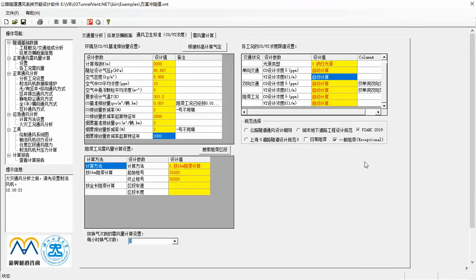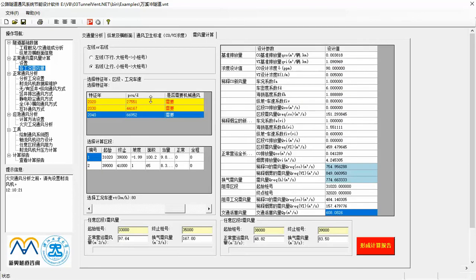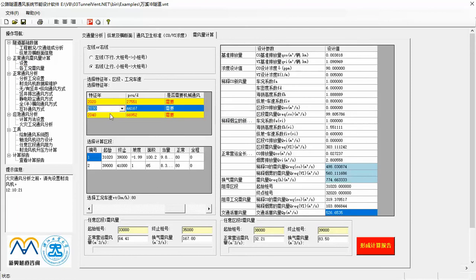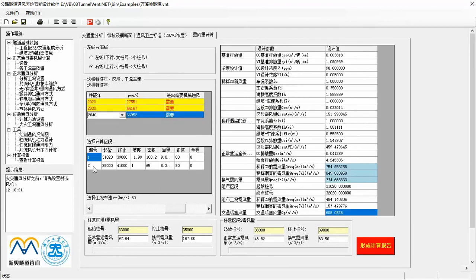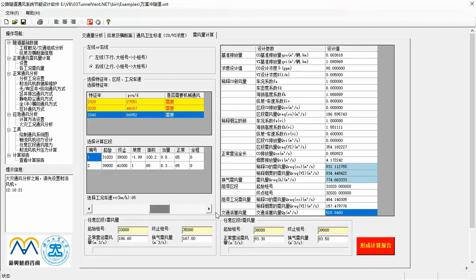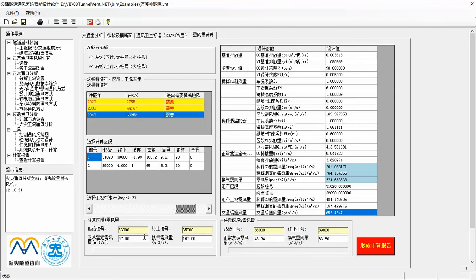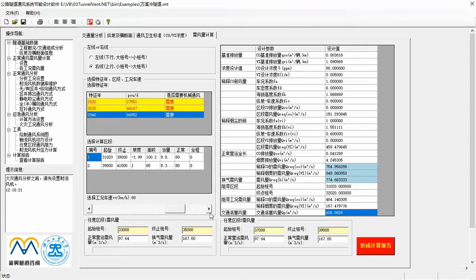Then, after all the necessary data are input, you can get the air demand results for any tube, any future year and any section which features different gradient, cross section. In the right table, you can check all the results, including basic emission value, concentration value, air demand value of selected section and the whole tunnel. The highlight of this module is jet fan effect air flow result calculated by the software. It is the base to judge whether natural ventilation can completely meet normal operation.